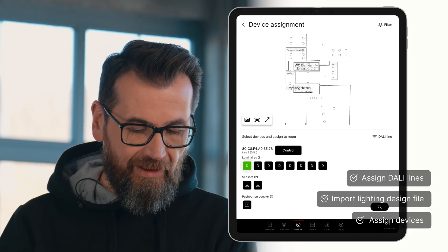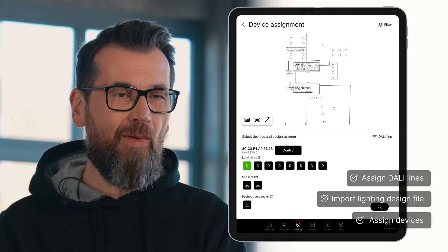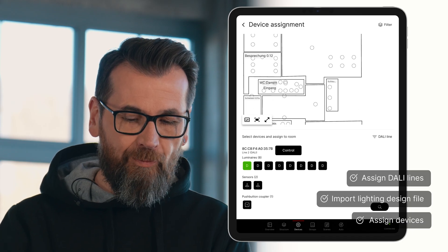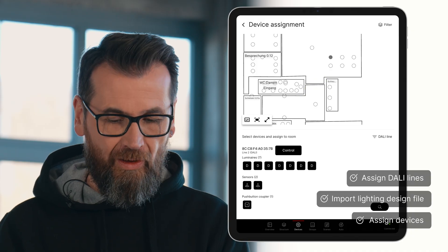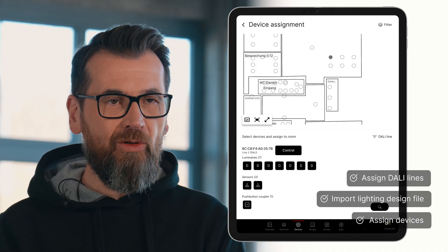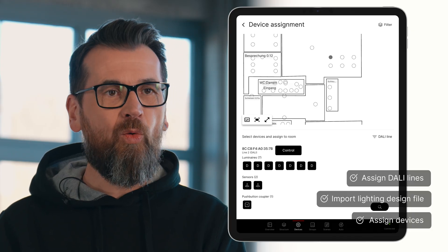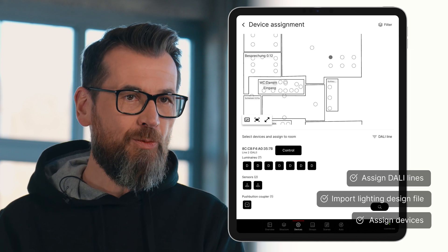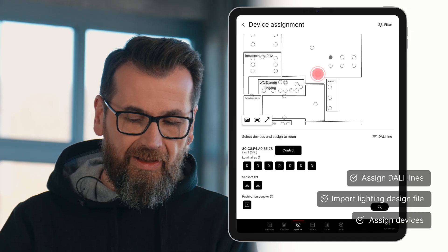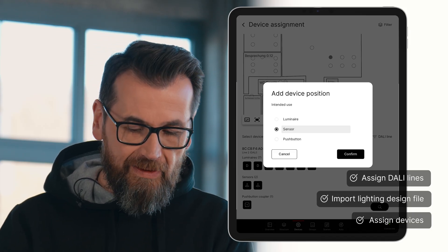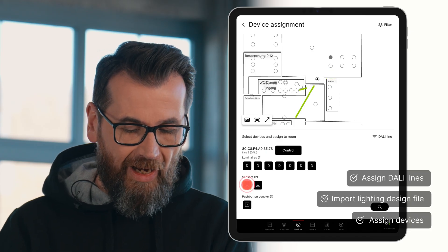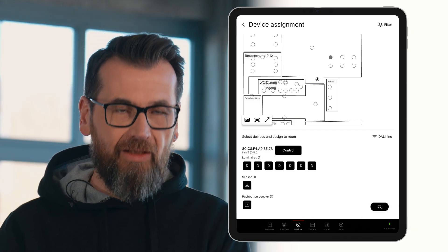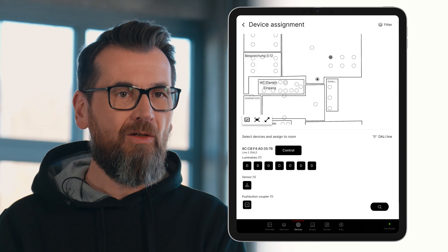We select a DALI luminaire. It provides feedback in the room by flashing, and I can then easily place it into the building plan by tapping a luminaire position in the plan. Of course, I can also remove it from that position again. I can add positions as needed and flexibly assign all my DALI devices into the building plan. Here, for example, we can see that there are no sensors in the building plan. To add this missing sensor position, I simply tap on any spot in the building plan, insert the sensor position, and can now place one of the connected sensors into the plan. We then continue this process with all connected DALI devices and apply it across all DALI lines.